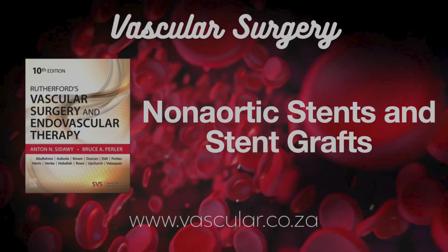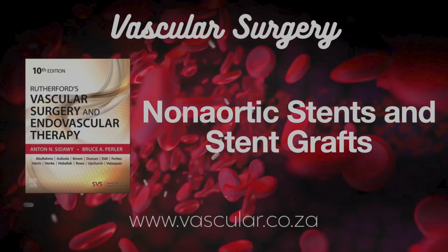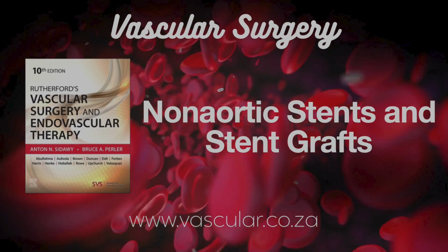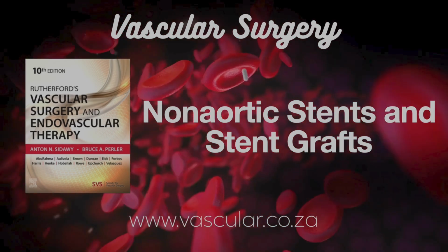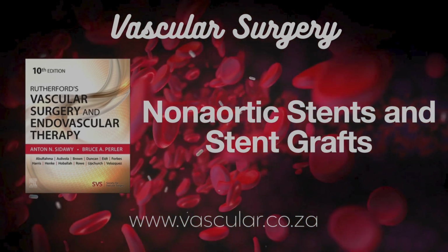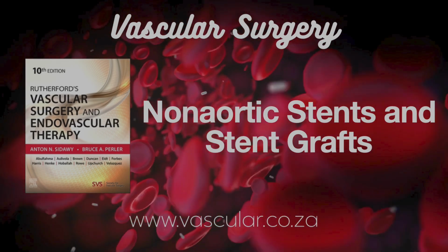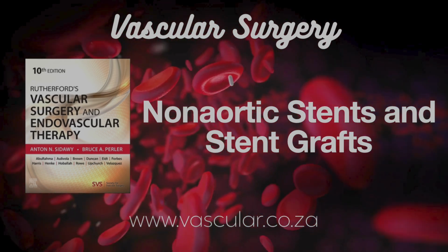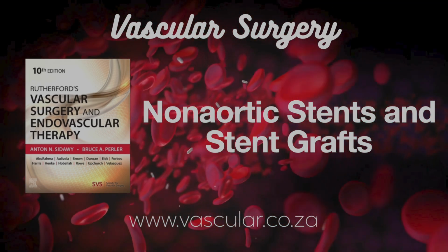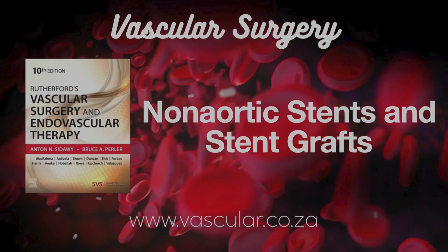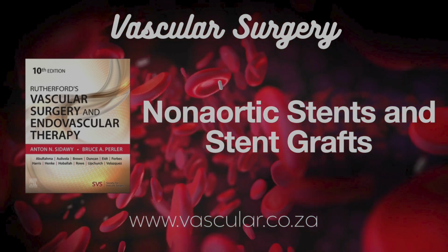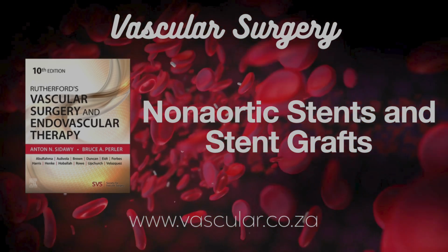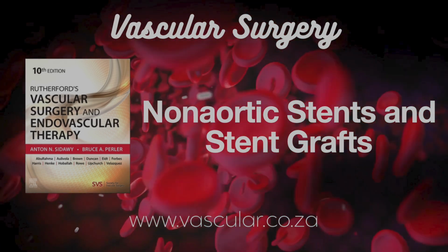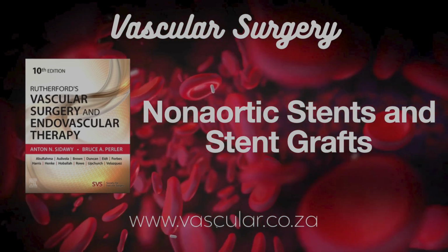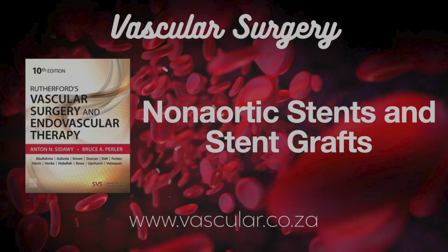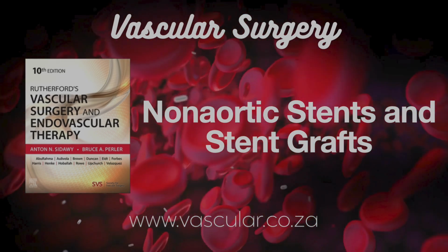Now, within the stent mesh itself, there's this idea of cell design. Open versus closed. Right, the pattern of the gaps. Closed cell stents have small, connected gaps, like a fine mesh. Benefits: more uniform wall coverage, maybe better at trapping debris so it doesn't float downstream, embolization. Downside: less flexible because it's all interconnected. And open cell? Like a chain link fence, you said. Exactly. Larger gaps, less connected, much more flexible, conforms better to vessel shapes. Right.